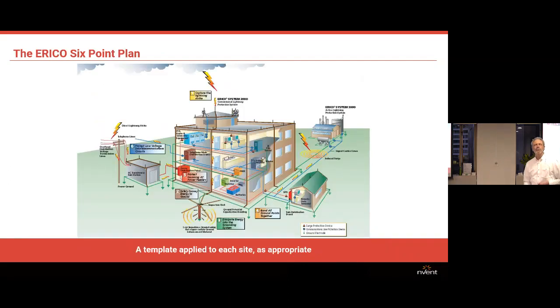Right, around that building, so what I was just describing there is the active lightning protection system, the Dynasphere system typically, but not always. Alternatively, conventional lightning protection is made up of rods around the edges and across the middle of the building, and you can see those around the top edge, and there are a number of down conductors going down to an earth system at the bottom. So that's two approaches to direct strike lightning protection. Also shown in there are separated earthing systems, and there's bonding between them and bonding between the surge protection that's there. So that's an overview plan.